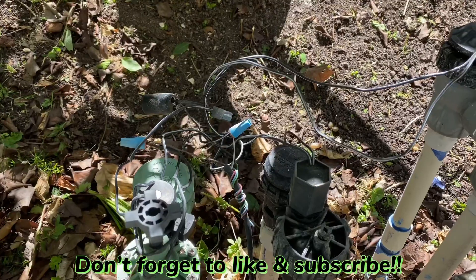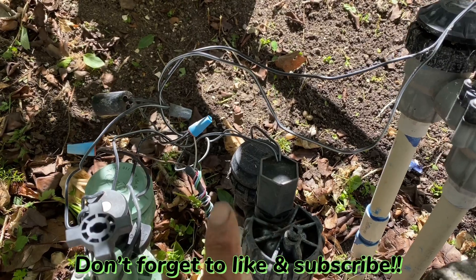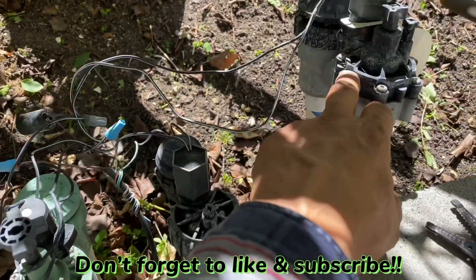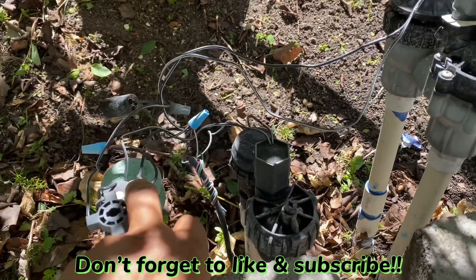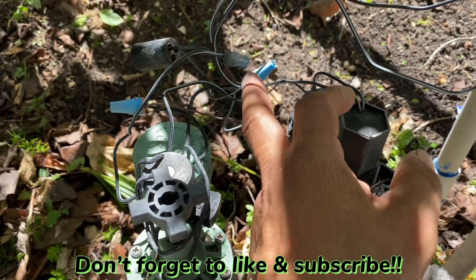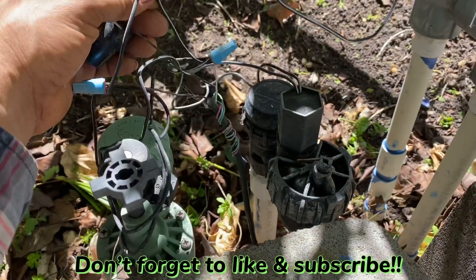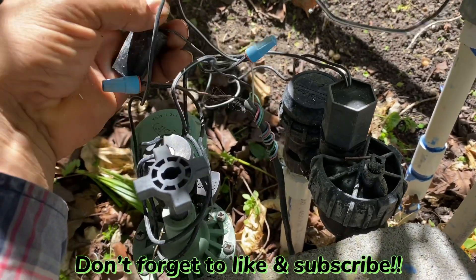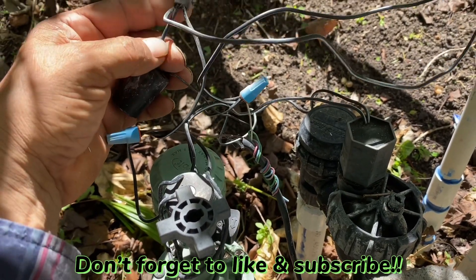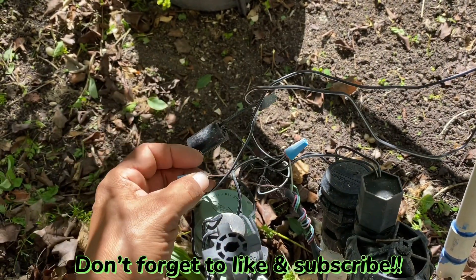A little tip on making the switch on the wiring here to get the opposite going on. We said that these two are connected right now and this one is by itself — we're going to do the opposite. When you're switching, don't worry about the common wire. You don't have to undo that, just leave it alone. It's just the wire where you have your voltage coming from. Take this off here and just switch it to this side.